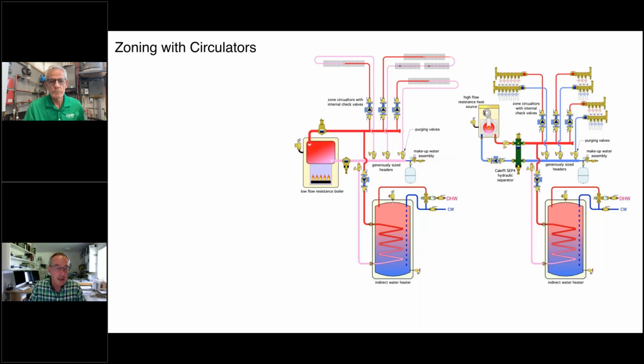Down at the bottom, we've got an indirect water heater. Now, that's a conventional boiler that has low flow resistance. So if we had all 4 of these circulators on at the same time, we don't have much pressure drop through that heat source or through those headers. And you can see the note here, it says generously sized headers. That's important. We want to keep the pressure drop or the head loss through those headers very small, because what that gives us is a quality called hydraulic separation.